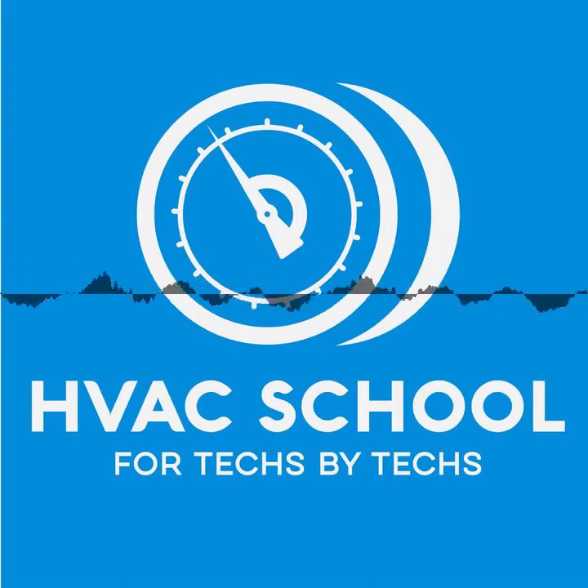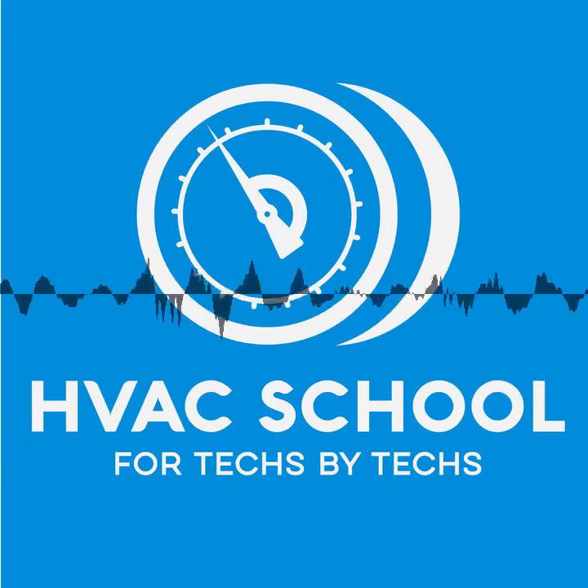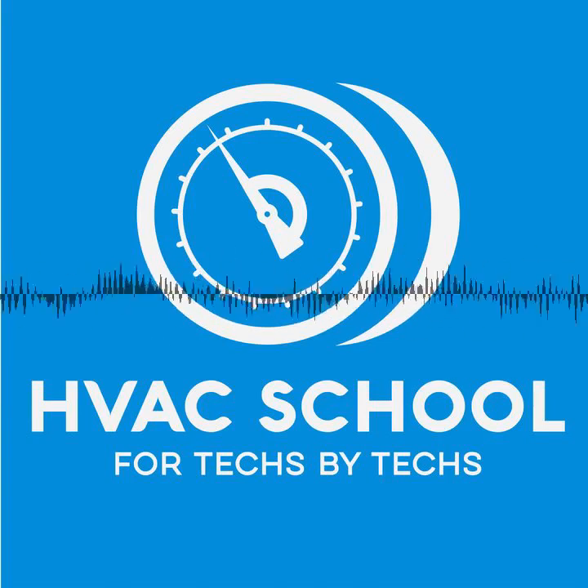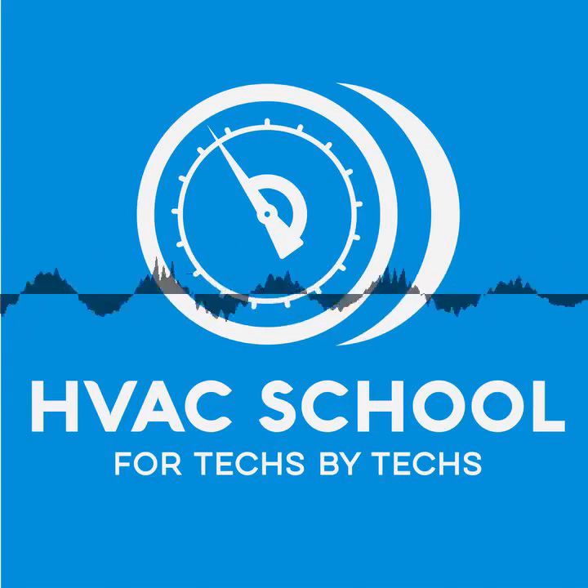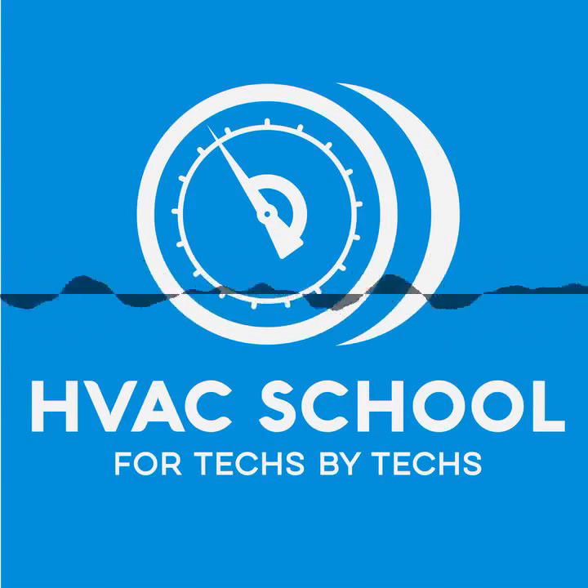We're looking forward to getting more electronic expansion valves out there because they eliminate a lot of the issues of having to sit down and fine-tune superheat. If you look at the time a tech spends fine-tuning superheat on certain evaporator designs, trying to find something as low as possible while still stable — the EEV does all that work for you. Labor is not cheap these days, so there's a benefit from a time-saving standpoint. There's also the benefit of being able to track data — you have communication to a module or a data log, so if something goes wrong, you can go back three or four days and see exactly where issues started.